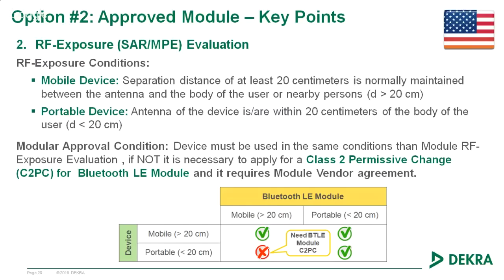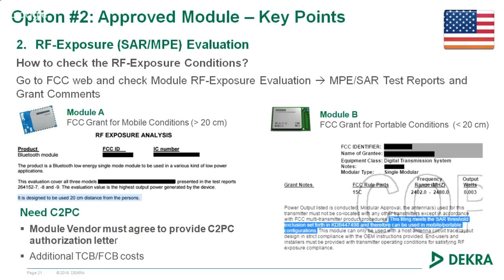Okay, this is an example: module A has been evaluated in mobile exposure conditions. Now when I place it in a wearable device close to the body, I will need to modify the certification of the module to be able to use it. It does not mean that it's not possible. It means that you need to do an additional procedure with the FCC, and it will have an additional cost. For instance, module B has already been evaluated in portable conditions, so I can use it with the user less than 20 centimeters from the radio, and I can go directly and inherit the module certification completely.